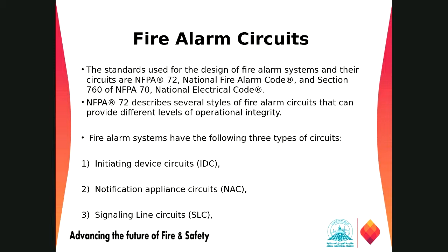It is still in use in some hotels and some small areas, but in most cases now everyone is going with the addressable one, which is more advanced than the conventional, old style one. In the addressable, the control panel will let you know the exact location. Addressable will use the SLC and NAC circuits.